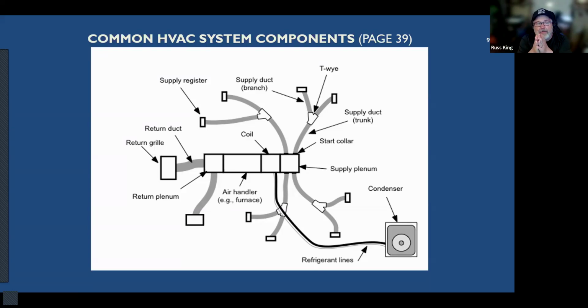But some ducts will come out and then they'll have to split. All right. And we call that a trunk. Any duct that splits into more than one duct is called a trunk. And you can have supply trunks and return trunks. Okay. And so this duct comes out here and it splits. And so that's a trunk. And this goes to the register. So that's a branch and that's a branch, just like a tree, right?